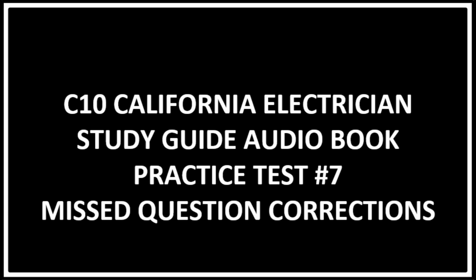Service with number 2 or smaller wires, copper ground will be number 8. Service with number 1 or number 0 wires, ground will be number 6. Service with 2/0 or 3/0 wires will have ground of number 4.